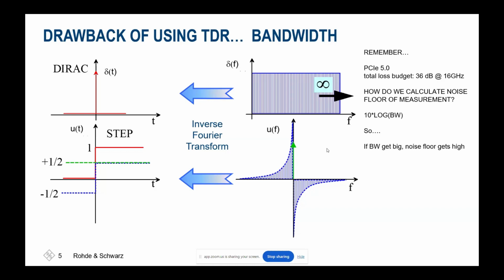So if I have a megahertz signal, I take kTB, which is minus 174 dBm, and add 60 dB, since 10 log of a million is 60 dB. Now my noise floor went from minus 174 up to minus 114, so I can't measure anything lower than that. And realize that no instrument is really down as low as minus 174. If I go to a gigahertz wide signal, it gets 30 dB worse, et cetera.